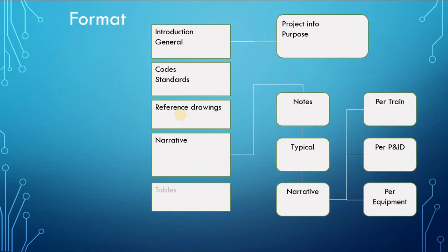The reason is that each PNID has its own life cycle. If you take revision 1 and make your control narrative, who said the process engineer will not update revision 1 to revision 5? Now your control system is based on revision 1, and you included the PNID of revision 1 in your control narrative, and you will never know that the PNID has been updated. So there are discrepancies between the documents. So I don't like to include the drawings in my control narrative.